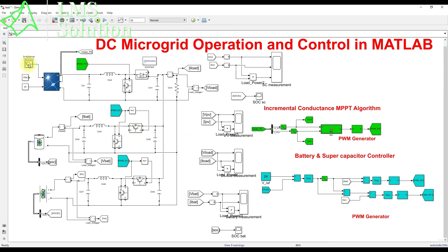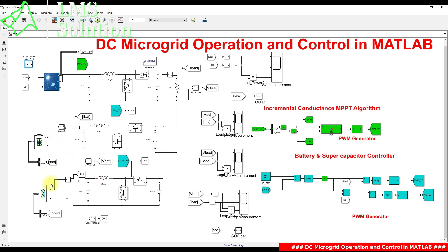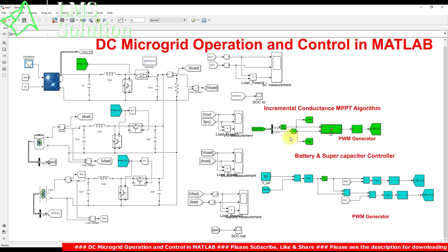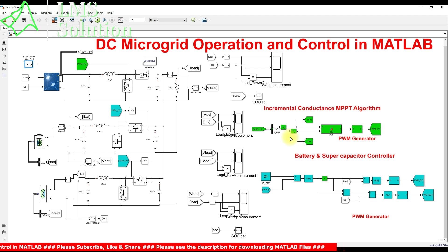To test the system, we create changes in irradiation condition for the PV panel. Every 2 seconds, the irradiation changes from 1000 to 800, 500, 300, and 100 W/m², then increases back through 300, 500, and 800 W/m². We will check the PV voltage, current, and power; battery voltage, current, and power; supercapacitor voltage, current, and power; battery SOC; MPPT tracking; and DC bus voltage regulation.